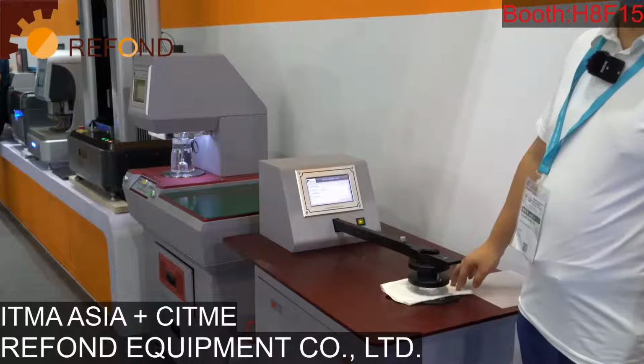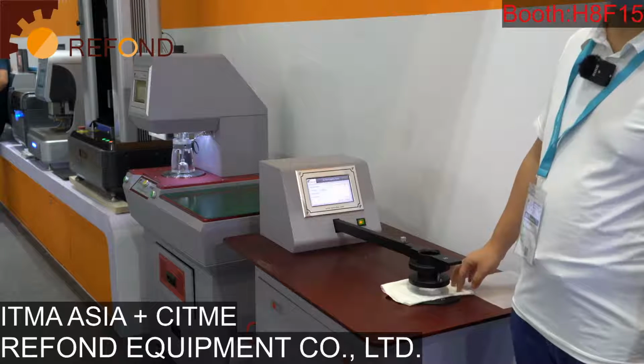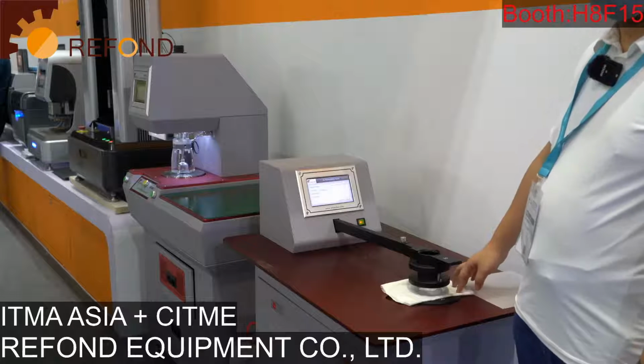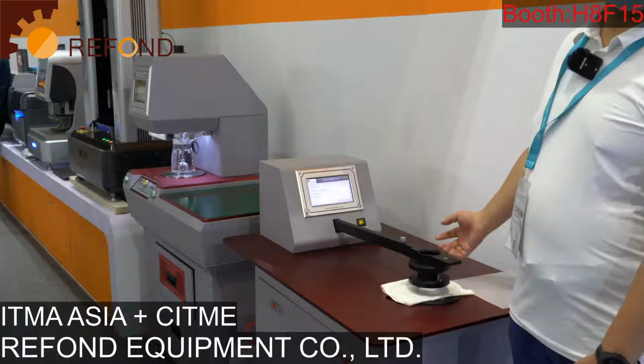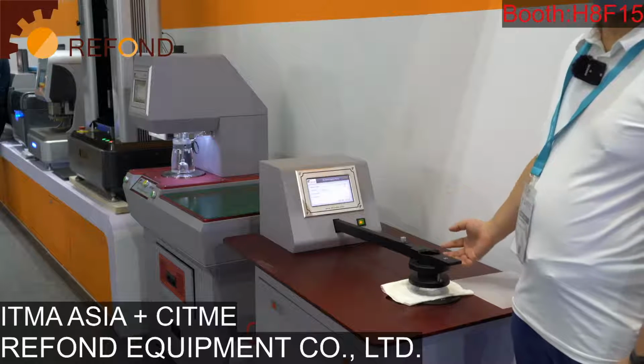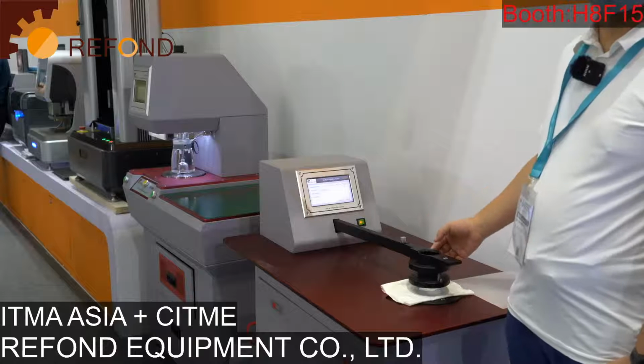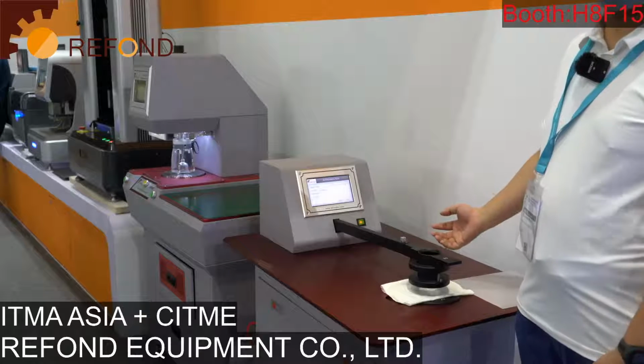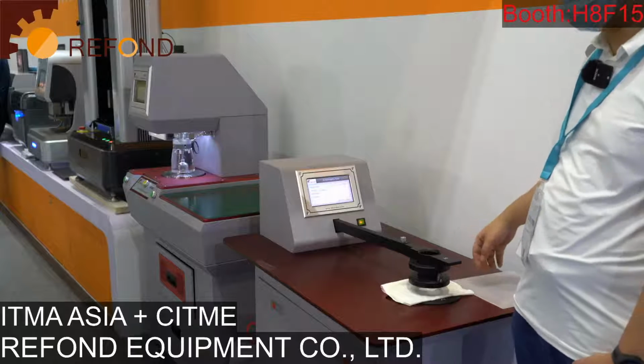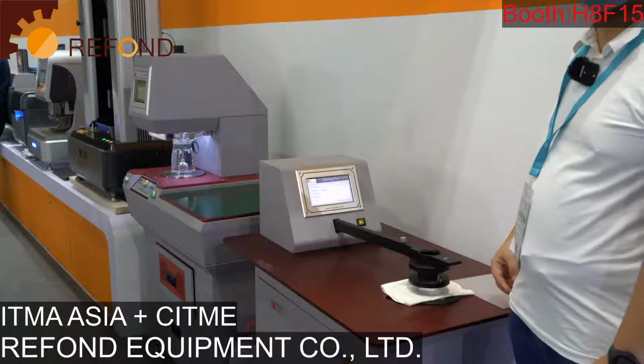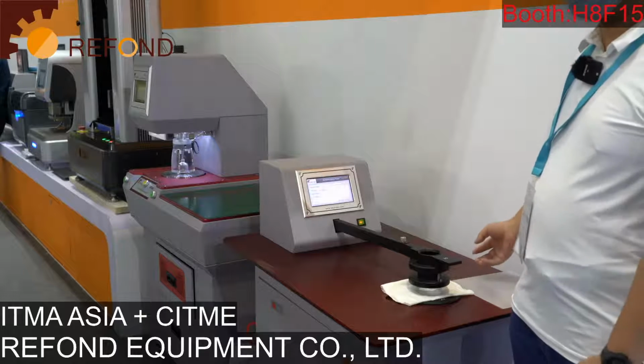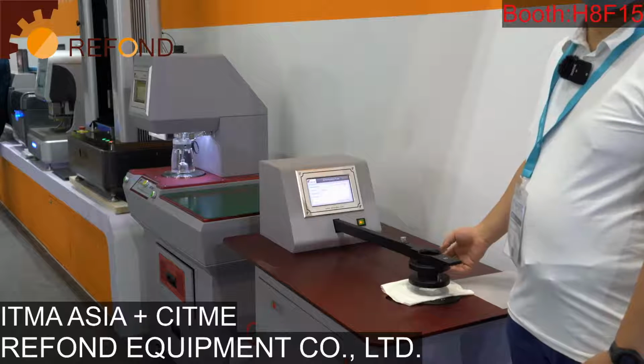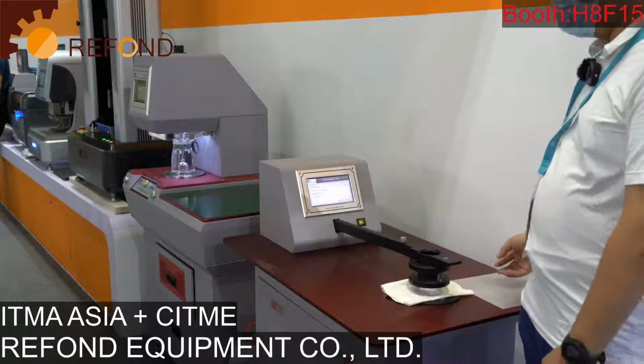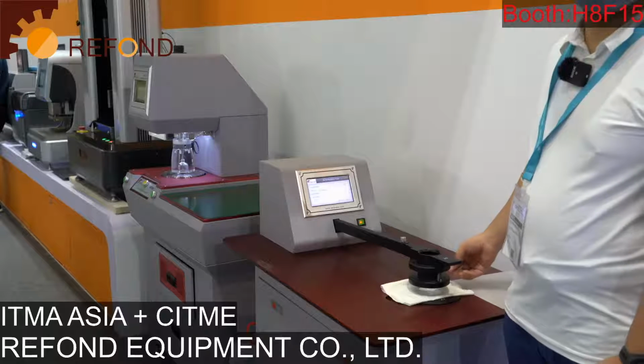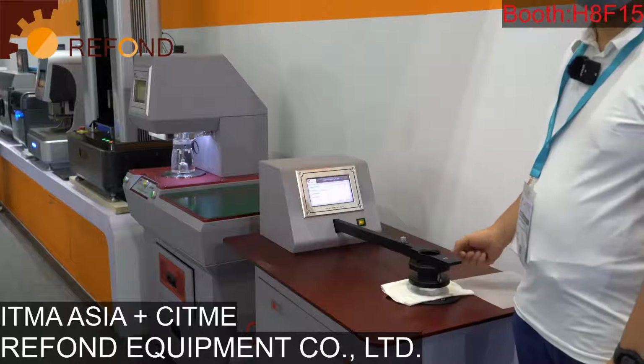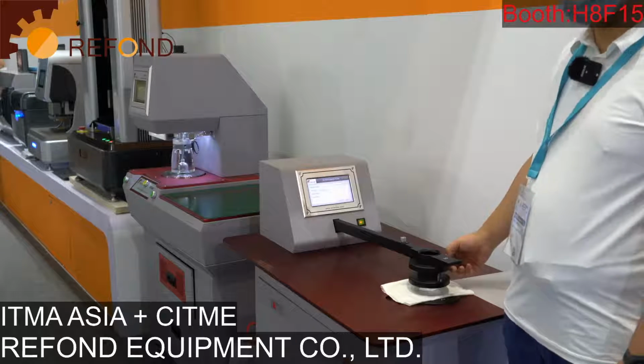The most important innovation for our new machine is that you can use an external calibrated airflow sensor or an airflow meter to calibrate the airflow for this machine. This produces better traceability than the traditional method of calibrating. The traditional method requires a different set of plates, which is more labor intensive, and also it cannot provide much traceability. Now we can use flow rate meters to calibrate this machine.